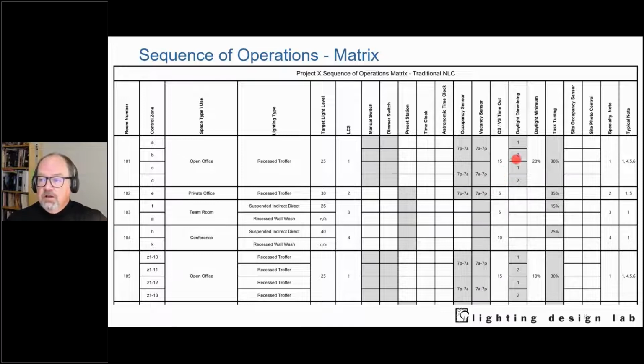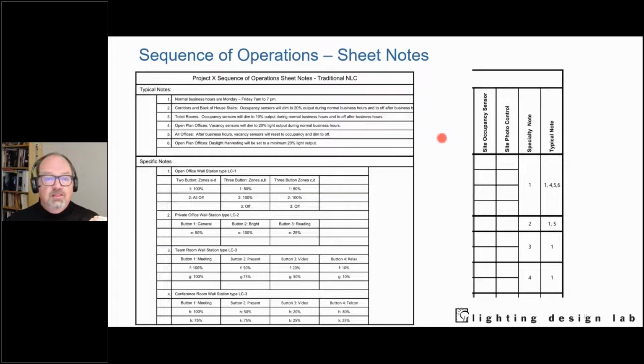Timeout information, what daylight dimming zone it is, the minimum daylight dimming percentage, task tuning. I'm going to task tune roughly down by 30% in this case to get to my target light level from my initial light level. And then I have these specialty notes that refer back to notes on my sheet, things like normal business hours, some information about corridors and back-of-house toilet rooms, and so on.